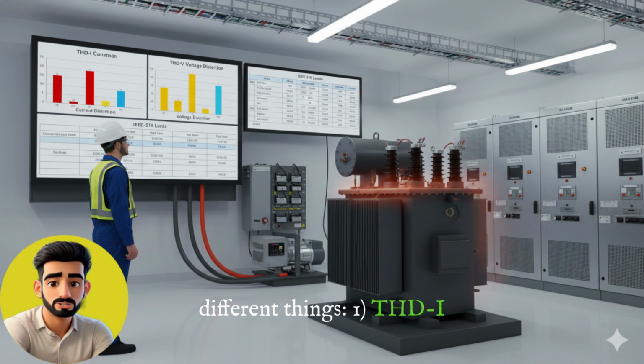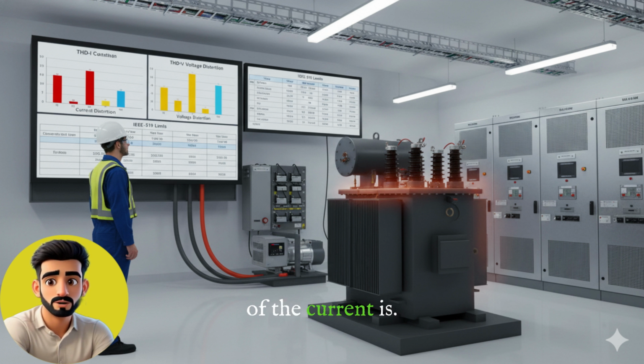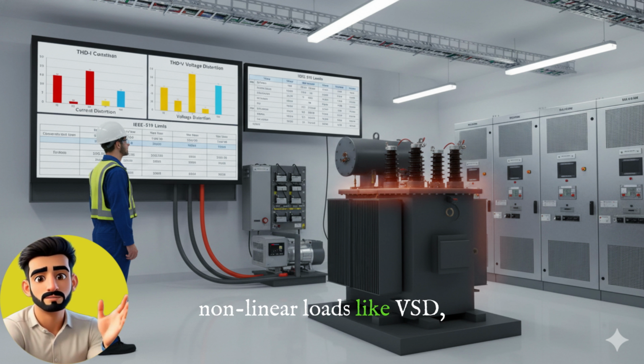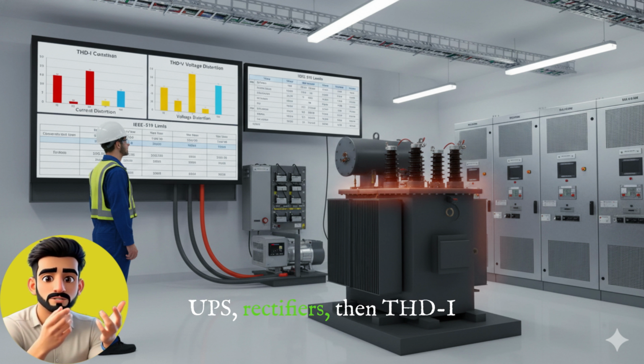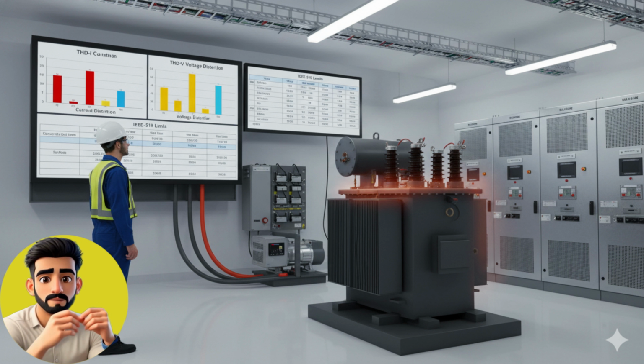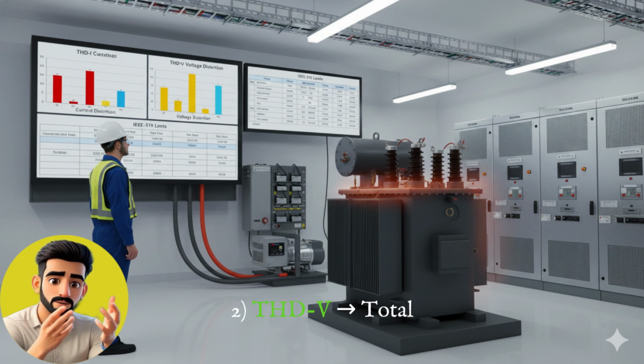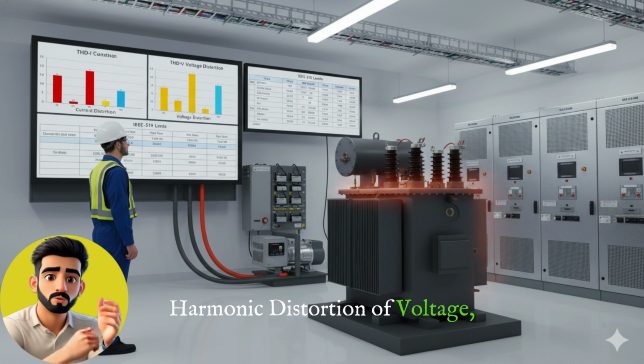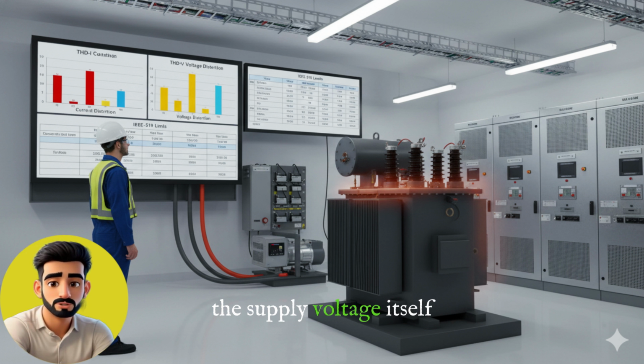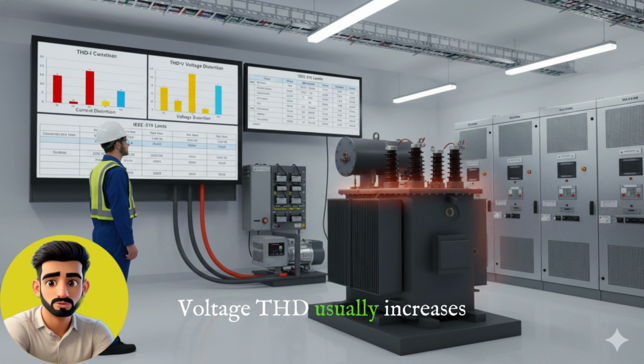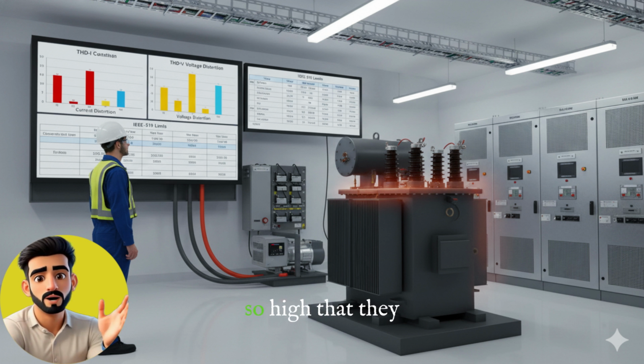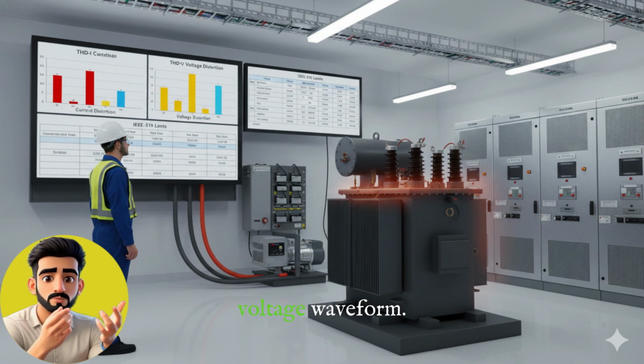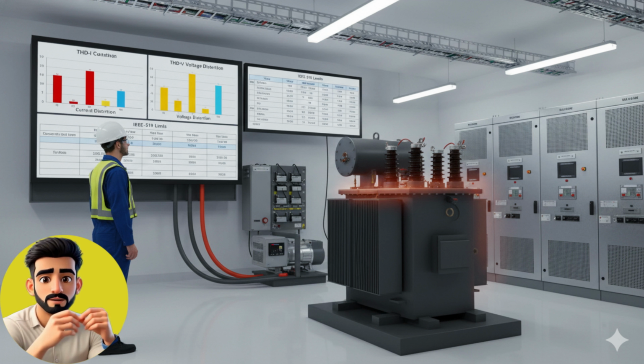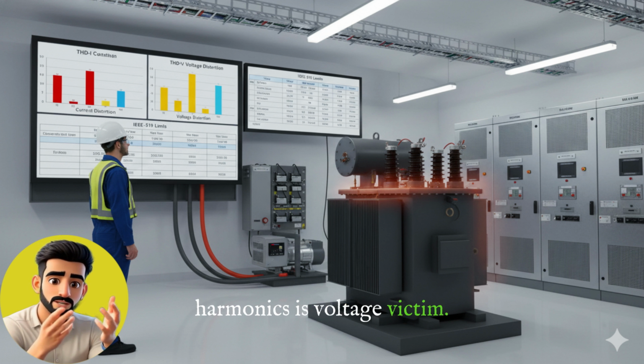1. THDI, total harmonic distortion of current. It shows how distorted the shape of the current is. If there are more nonlinear loads like VSD, UPS, rectifiers, then THDI is higher. 2. THDV, total harmonic distortion of voltage. It shows how much the supply voltage itself has become distorted. Voltage THD usually increases when current harmonics become so high that they also distort the grid's voltage waveform. So, friends, the root cause is current harmonics and the victim is voltage.